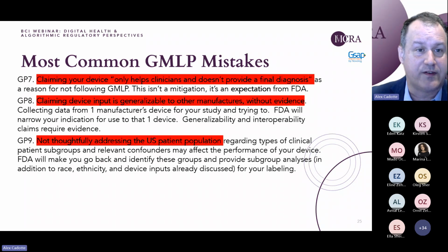Another common mistake that we see is claiming your device input is generalizable to other manufacturers. For example, if your device inputs x-rays from an x-ray system and you only tested it on one model from one manufacturer, FDA will basically offer you the ability to narrow your indications for use potentially to that one scanner from that one manufacturer if you don't demonstrate generalizability. So that's also an important subgroup consideration for your data set, to make sure that you've considered the range of inputs that you are going to claim that your device works with.